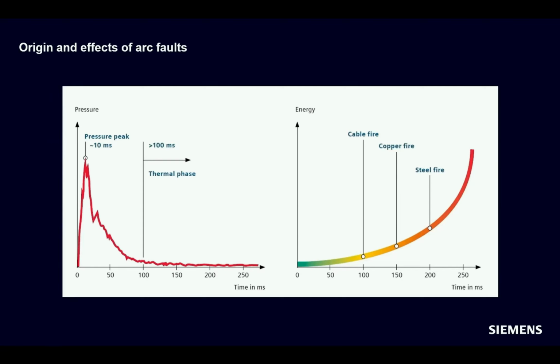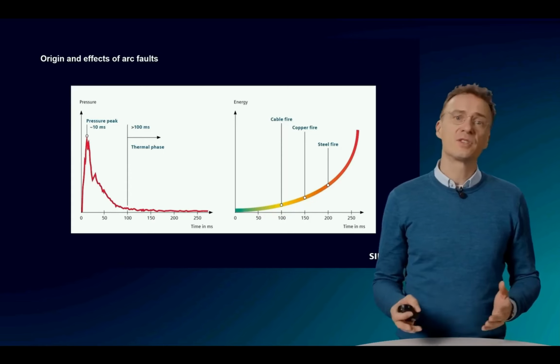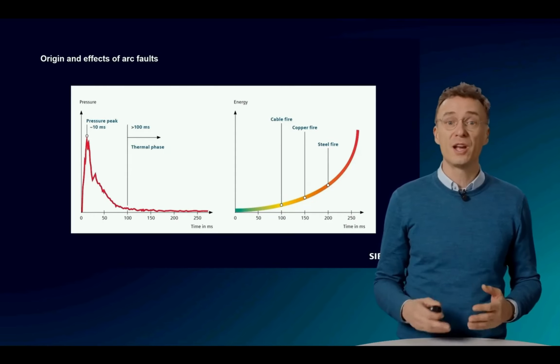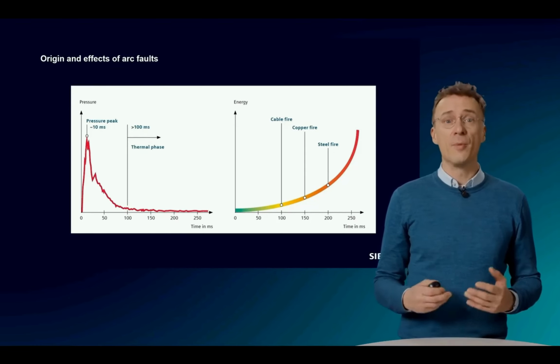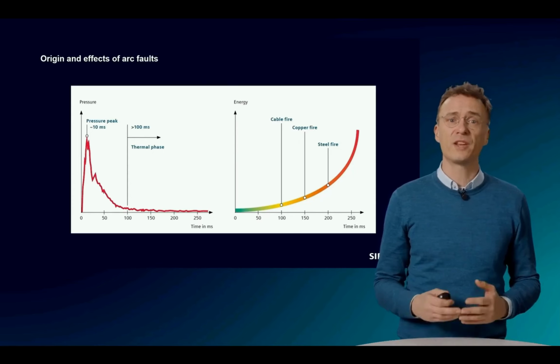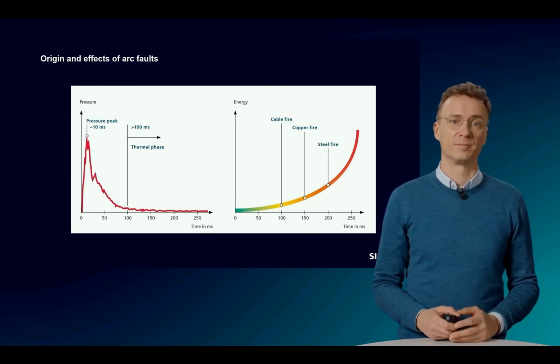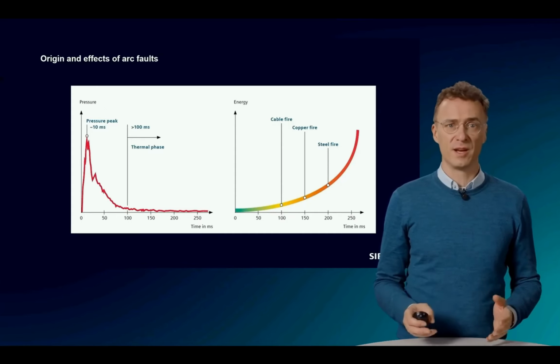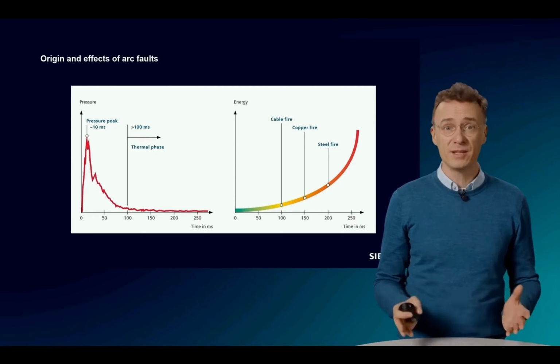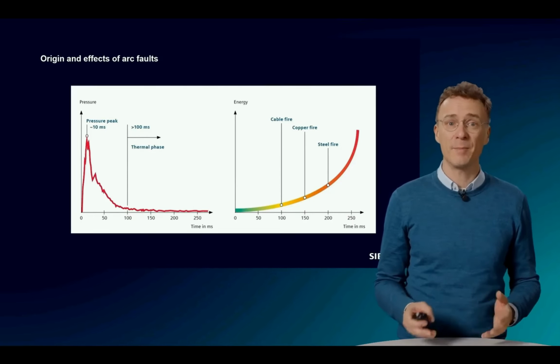The pressure rises rapidly, like an explosion. There's a bang. As a result, the temperature also rises sharply and can reach values of several thousand Kelvin. In addition, the high temperature also burns or vaporizes the material surrounding the arc fault. The first thing that burns is the insulation materials of the cables. Next, the copper, and after some 200 milliseconds, the steel of the enclosure can also start to burn. The burning materials may also produce toxic fumes that should not be inhaled under any circumstances. All in all, this is a very dangerous event, which can ultimately lead to serious, possibly even fatal, injuries to people and, of course, damage of electrical facilities.